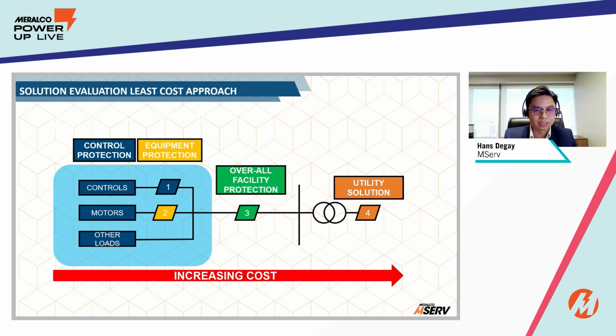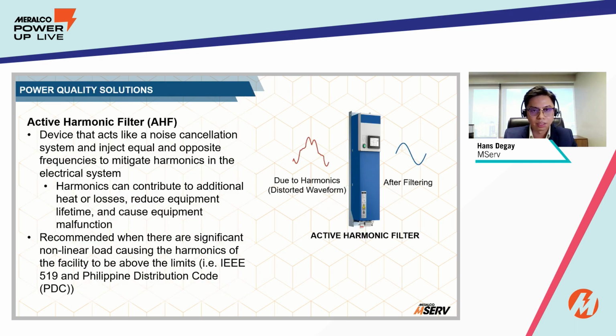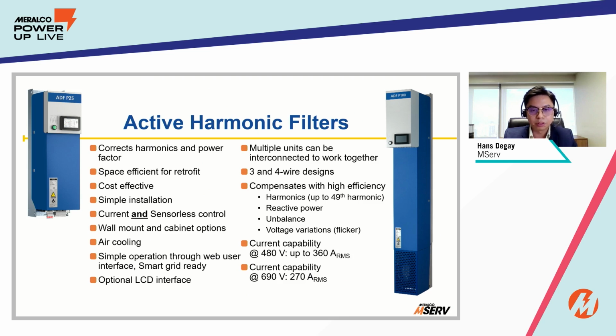So on the following slides, let's discuss some power quality equipment. First of all is harmonic filters, or active harmonic filters. Active harmonic filters can be related to noise cancelling headphones, which have a built-in microphone to analyze the noise waves and generate opposing sound waves to reduce the surrounding sound. For active harmonic filters, it actively monitors the harmonic levels and, via current transformer, injects opposing current to reduce and eliminate harmonics. There are multiple options, and we could size accordingly to the needs. They are very easy to install and easy to maintain. Active filters are constantly monitoring your current grid and putting out current to counterbalance the harmful harmonics. This results in clean power and smooth operation of your facility.